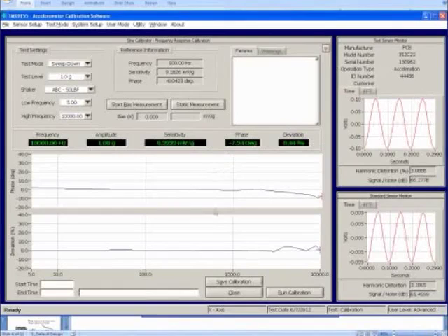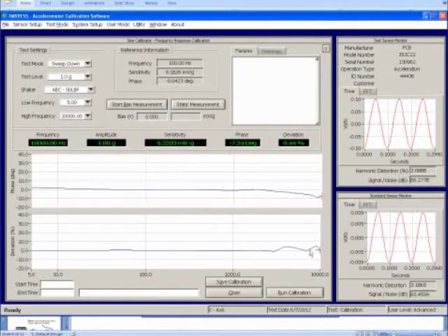So this guy is ref A. The little guy on top is ref B. For the sake of time savings, I've already done the first portion of the calibration. I have used ref A to calibrate ref B. And here are the calibration results. You can see a little bit of bumpiness in here, but let's just see what happens.